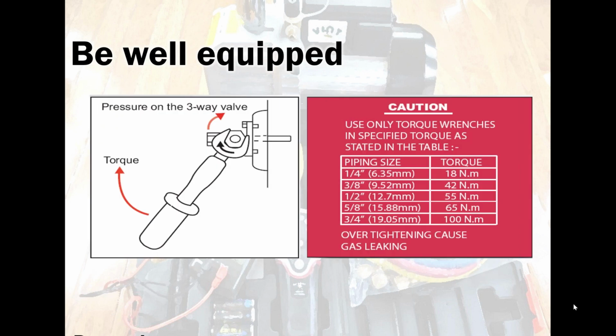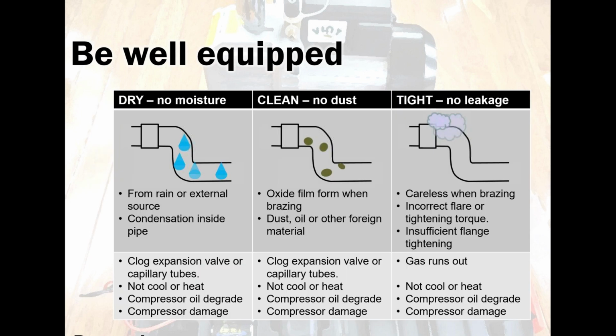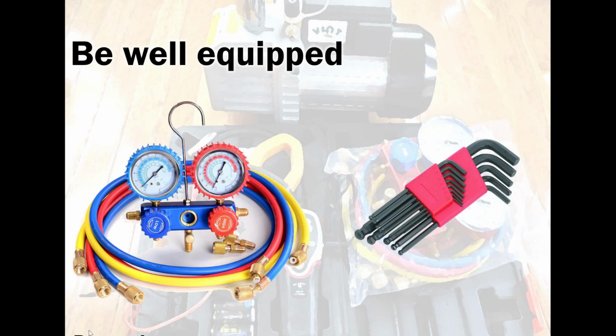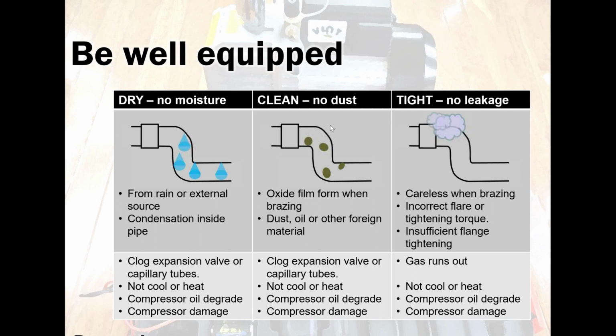In every box, there is an installation manual. And these are your values: 18 for quarter-inch, newton-meters, 3/8 up to 3/4. If your area is experiencing heavy moisture, high humidity, always go longer. Always vacuum the system longer. There is no harm, guys.